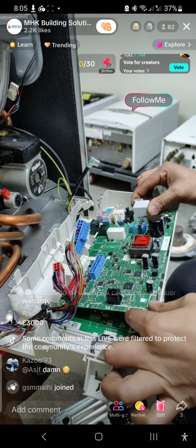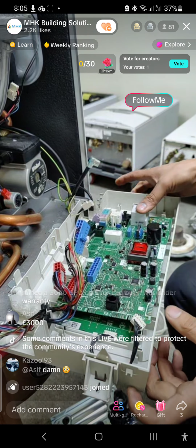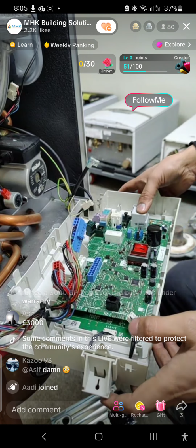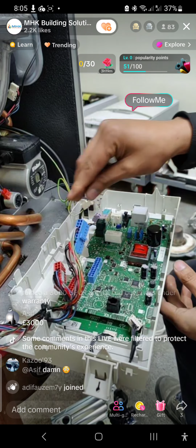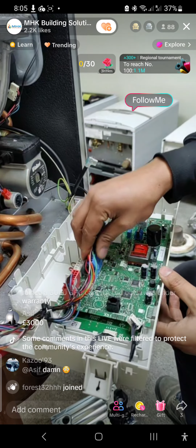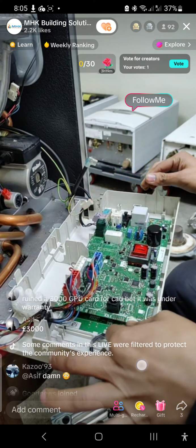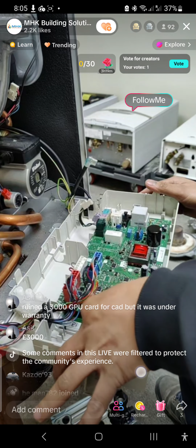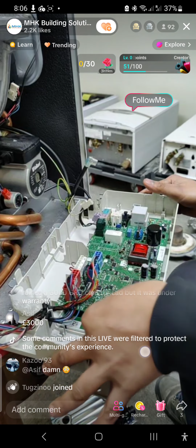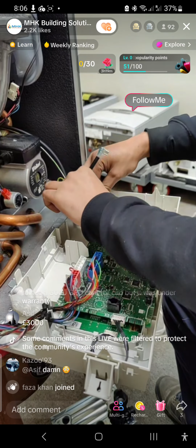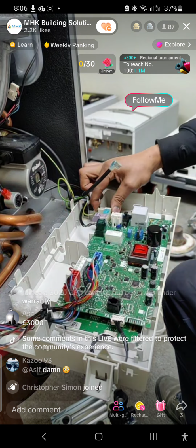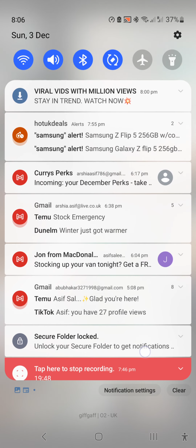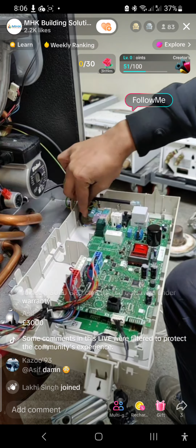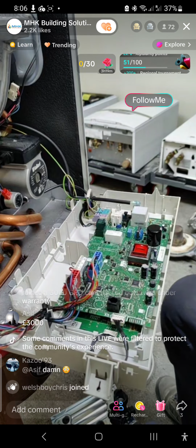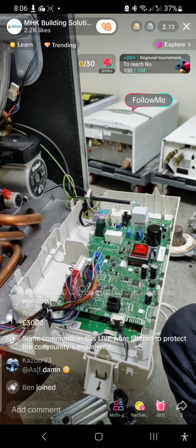Okay, so with the new PCB, it's just a matter of putting it back in reverse order. Place it back, clip it, all the connectors back in. Red goes to red, blue goes to blue. This white connector goes on where it came off from, that's on. Earth connector back on. Ignition electrode back in. And then that will leave us with this main connector here back in. That's how long it takes to replace a PCB on this.